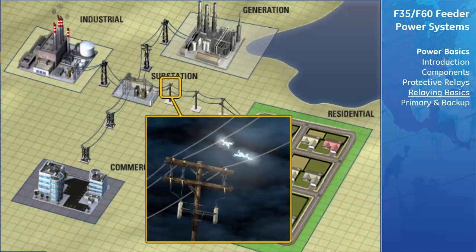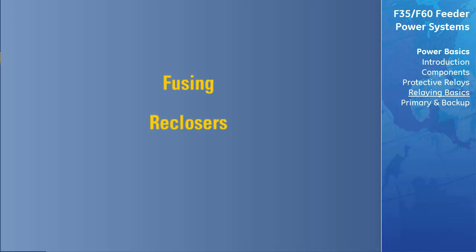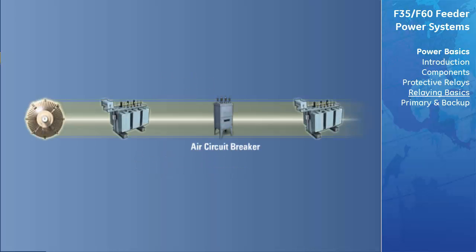Protective relays are not always part of a protection scheme. Fusing, reclosers, and sectionalizers are employed in some cases to keep costs down. Circuit breakers are located between each power system component, which makes it possible to isolate and disconnect the faulty component. If a breaker isn't installed between two adjacent components, both components will need to be disconnected for a failure in either one.